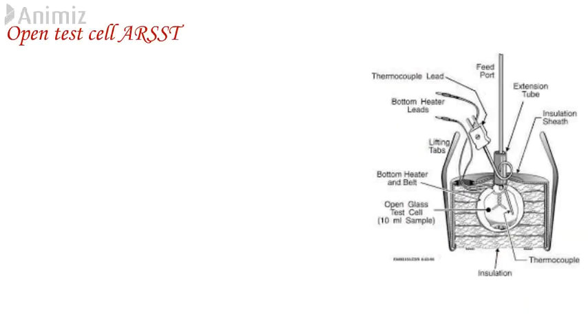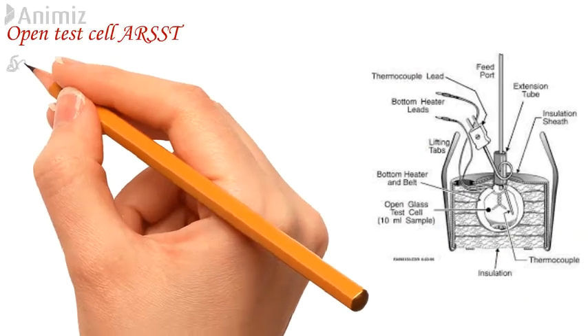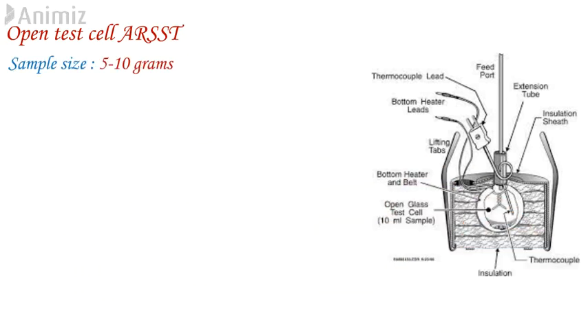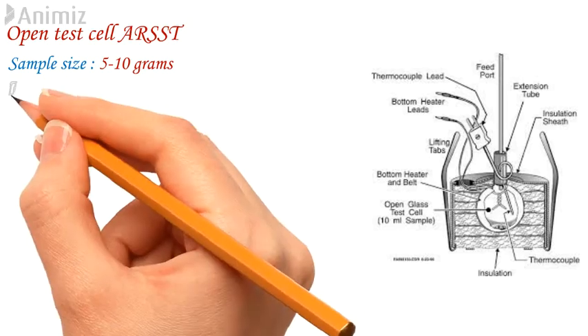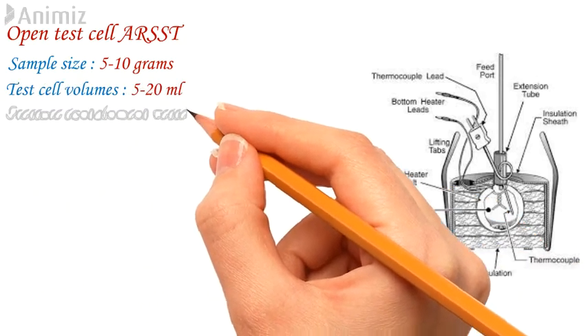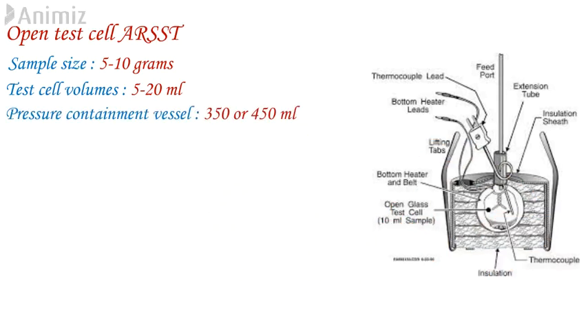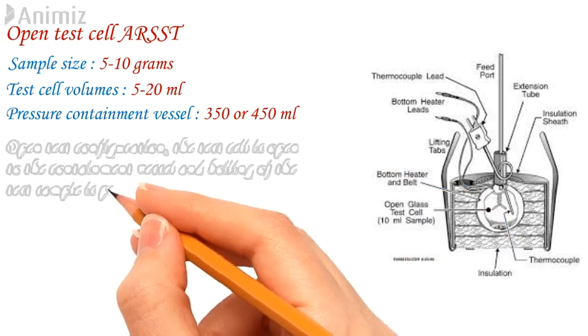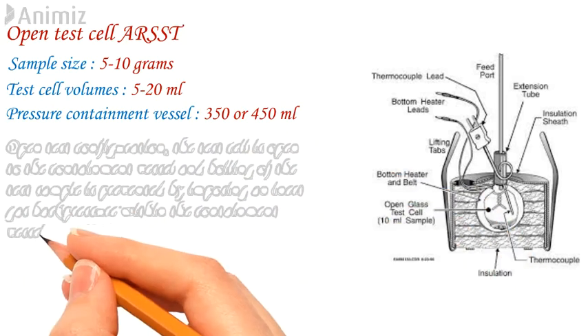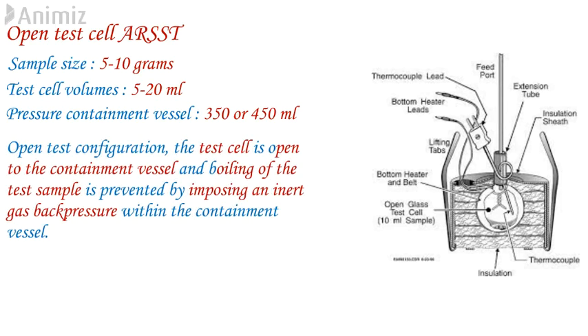Open test cell methodology: ARSST typically uses a relatively small yet representative sample size of 5 to 10 grams in a lightweight glass test cell with a volume of approximately 10 ml, though 5 ml or 20 ml test cells are sometimes used. The test cell is outfitted with a belt heater and installed in a 350 ml or 450 ml pressure containment vessel. In the open test configuration, the test cell is open to the containment vessel, and boiling of the test sample is prevented by imposing an inert gas back pressure within the containment vessel.